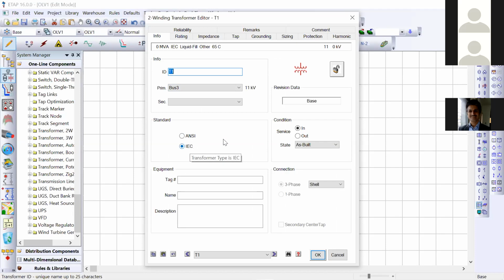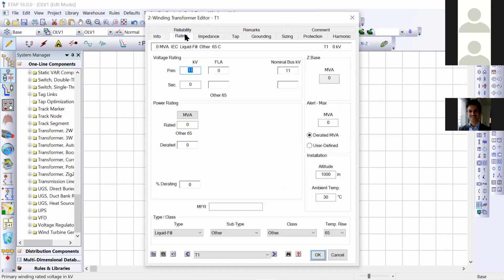Again, here I have to choose the IEC standard and the component condition, whether it is connected or not. These all things I need to give. This is transformer number 1. Now rating. See, the primary rating it has taken automatically. The secondary rating I need to give because this is the system which we are designing. As we know, all our distribution voltage level is 433 volt, so we are putting 0.433 kV as the secondary. Now the kVA rating I need to give. This is MVA or VA or kVA.